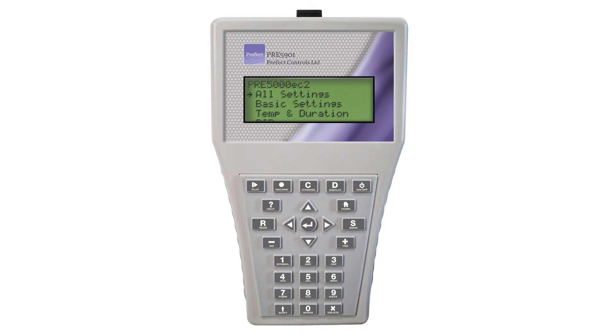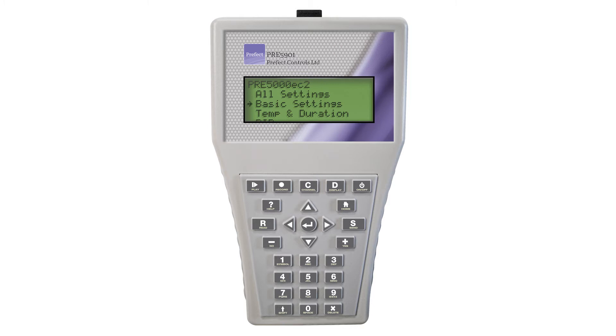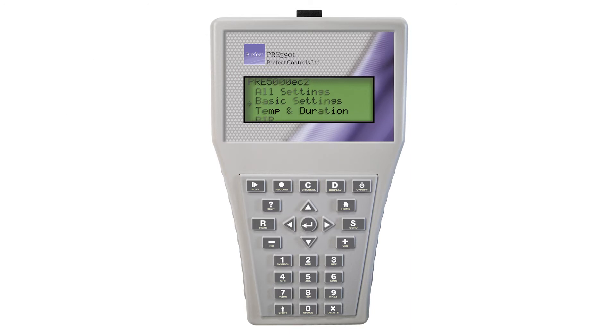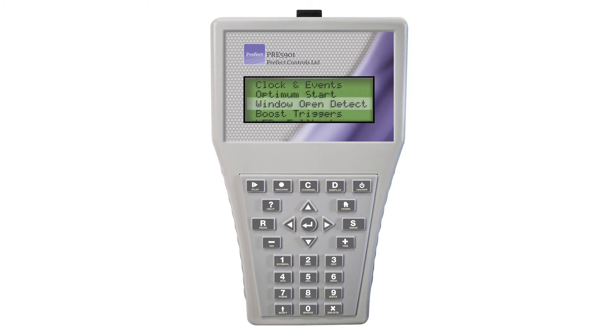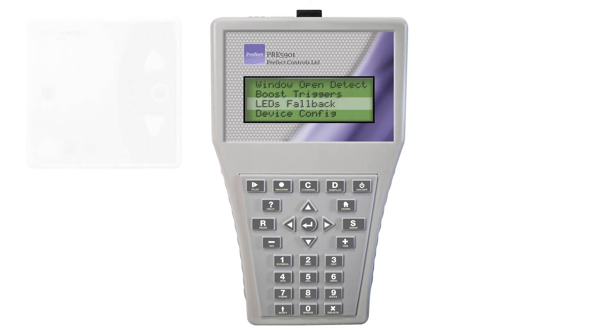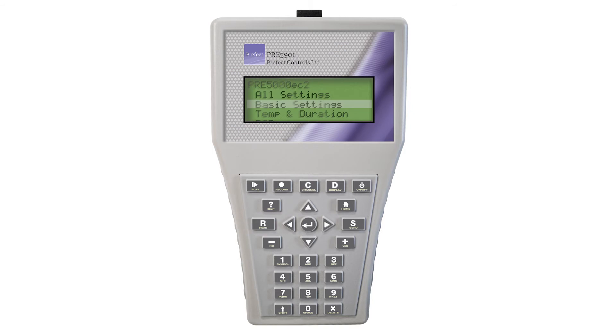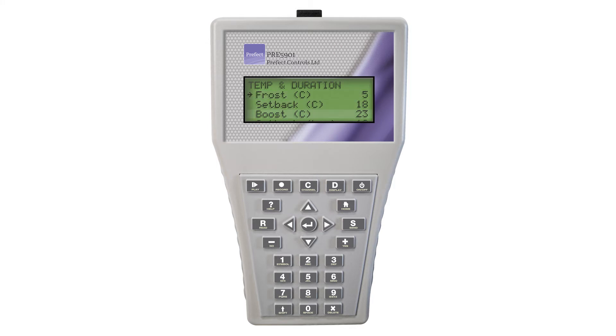All settings is only useful if you need to know all the settings within the thermostat or reset all the parameters. Basic settings groups together the most commonly used features, and this is where temperature, time, and PIR values are set. The items below basic settings are for specific functions — for example, window open detect and LEDs fallback, where the brightness of the LEDs of the thermostat can be adjusted. For the purposes of this demonstration, we will enter basic settings. Here you will find the parameters for frost, setback, and boost modes.